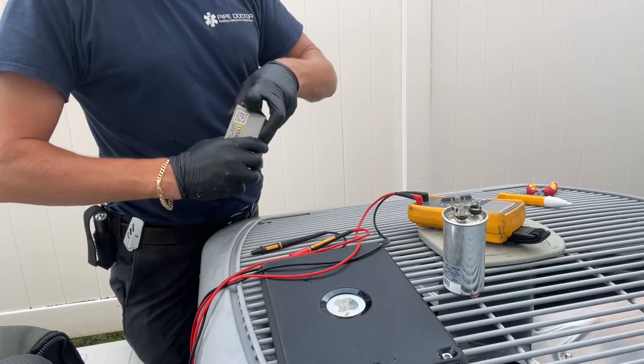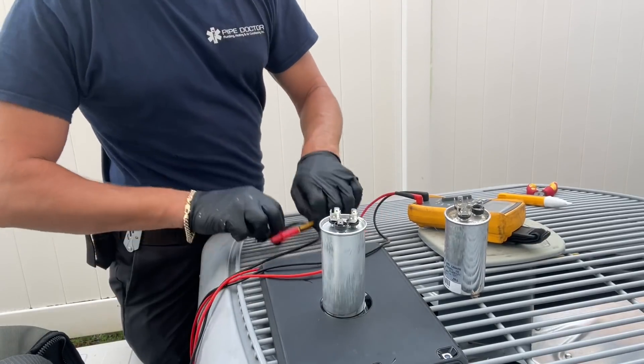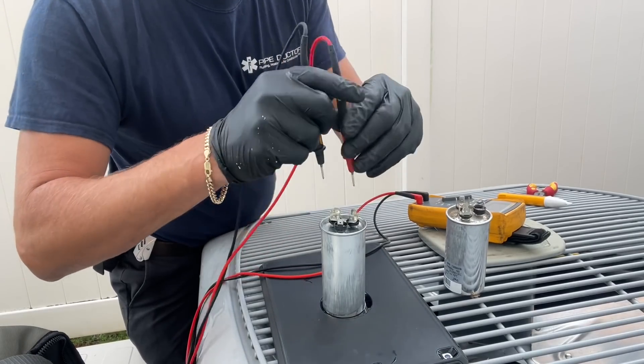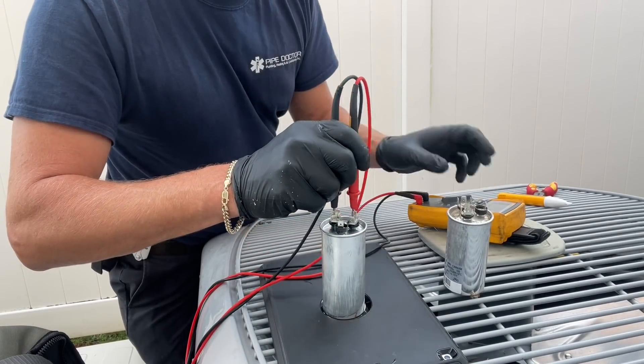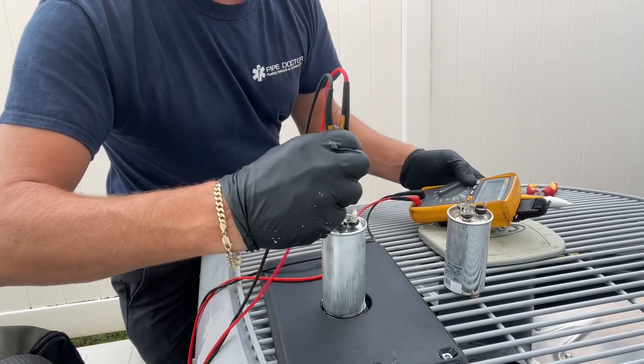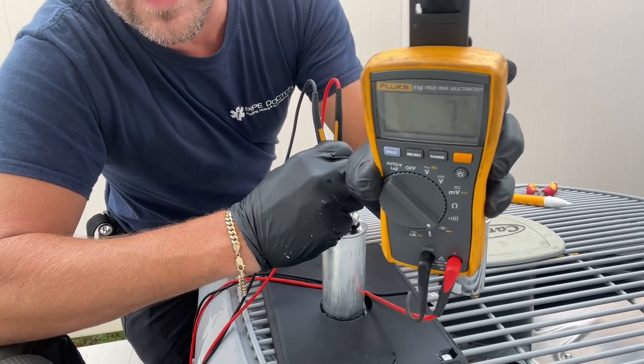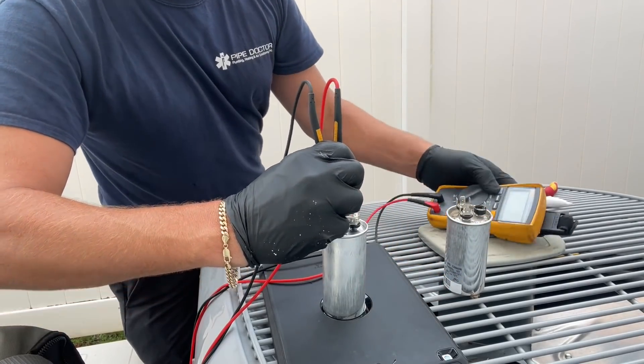It's not reading anything, so I've got a brand new one — it's another 30/7.5. Let's test that out. Common to Herm: I get 30. Common to fan: I get seven — should be 7.5. We'll blame that on made in China.